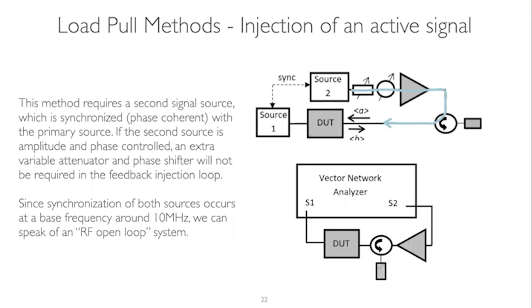So basically, what I was saying is you can control the amplitude and go as high as you want on the Smith chart, covering the entire Smith chart, versus the passive tuner which is limited in terms of loss. The A wave can only be as big as it can be in terms of amplitude, directly proportional to the loss. If you have a long cable or something between the reflected probe and the device, then the amplitude of that signal is limited by that.